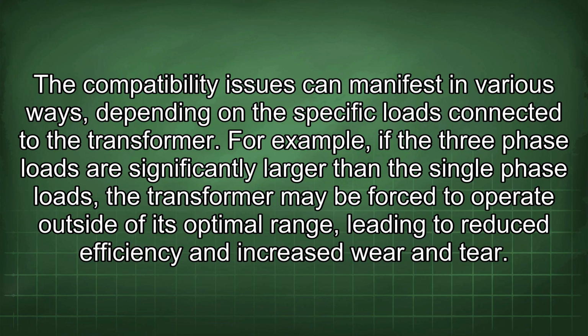For example, if the three-phase loads are significantly larger than the single-phase loads, the transformer may be forced to operate outside of its optimal range, leading to reduced efficiency and increased wear and tear.